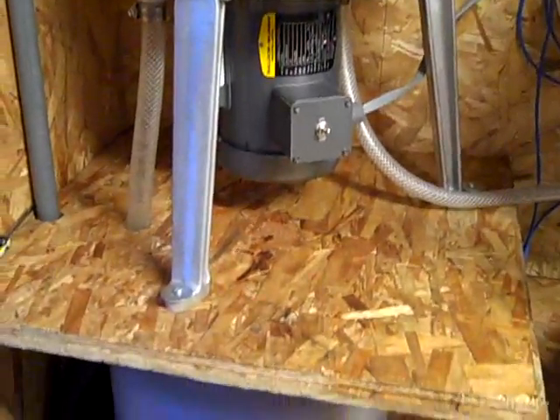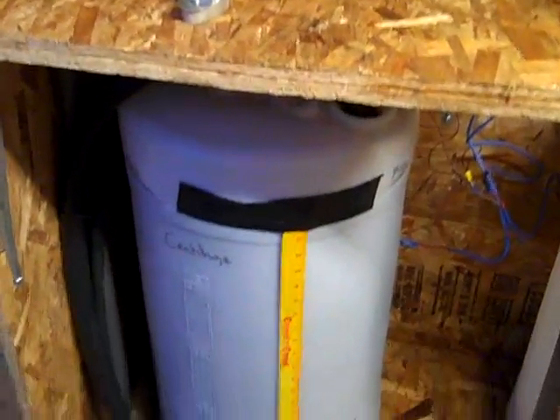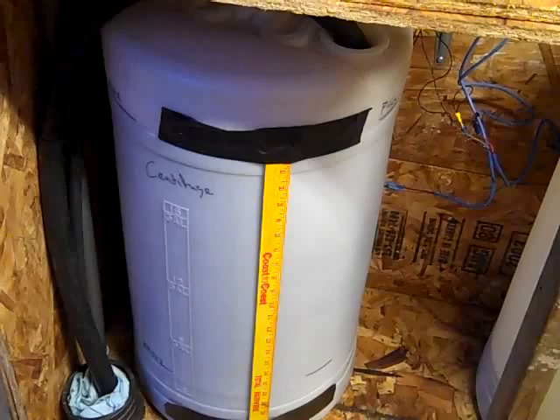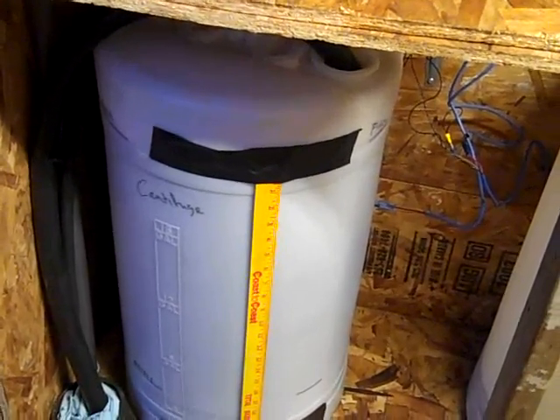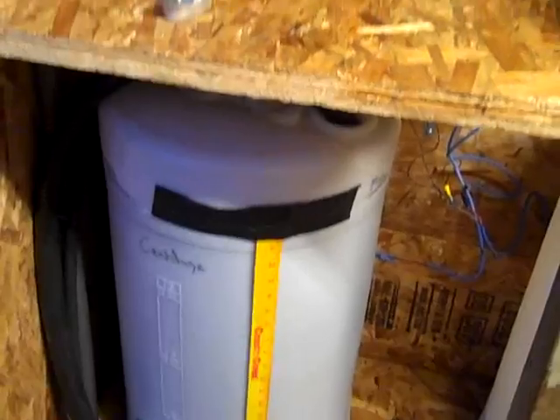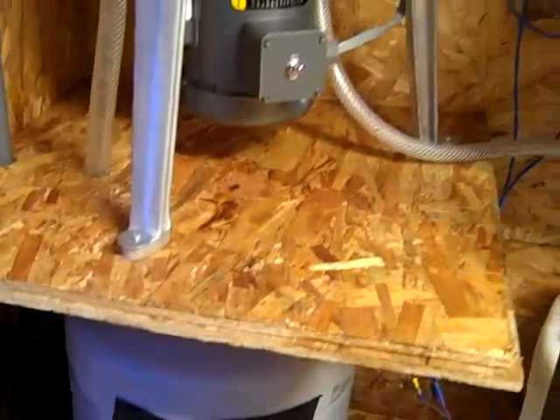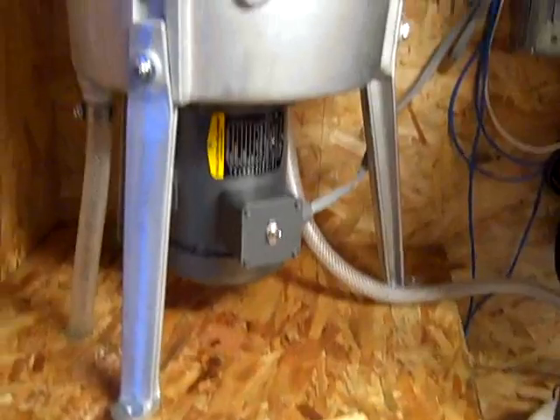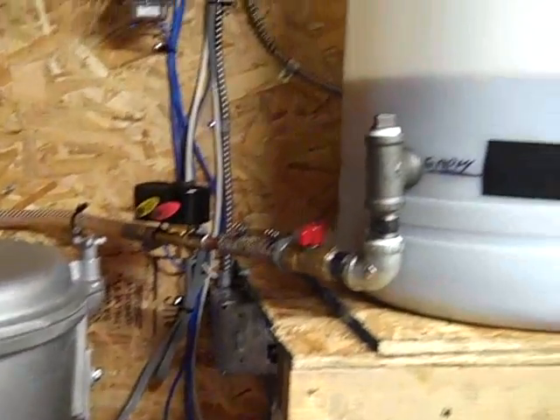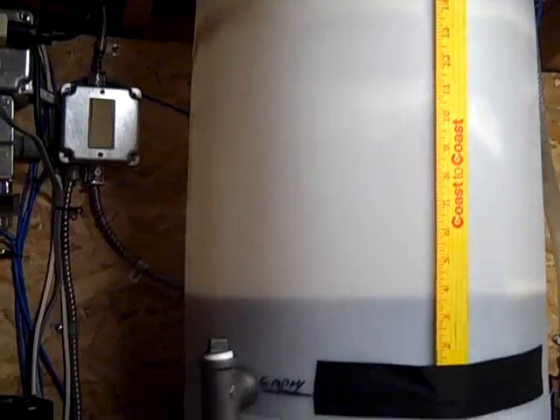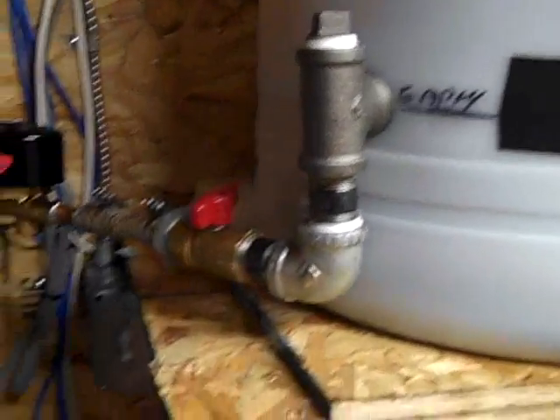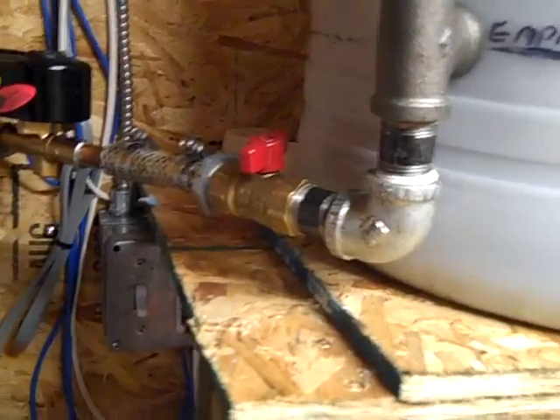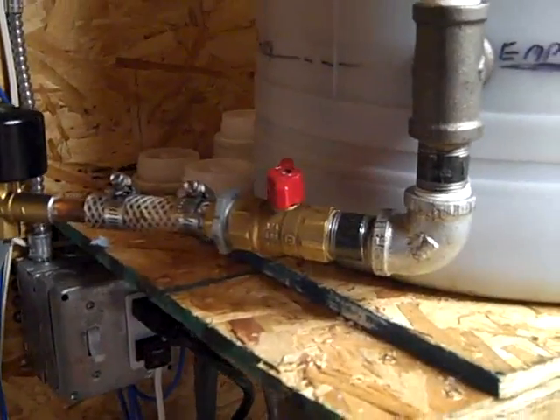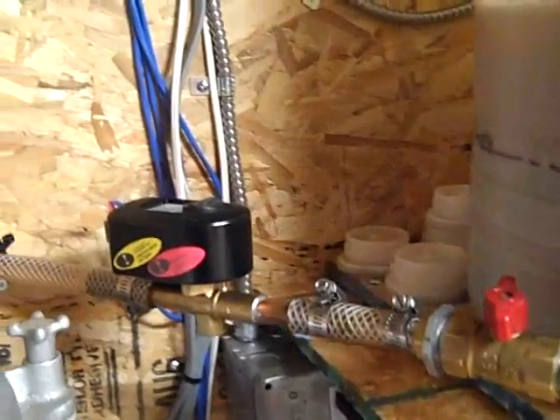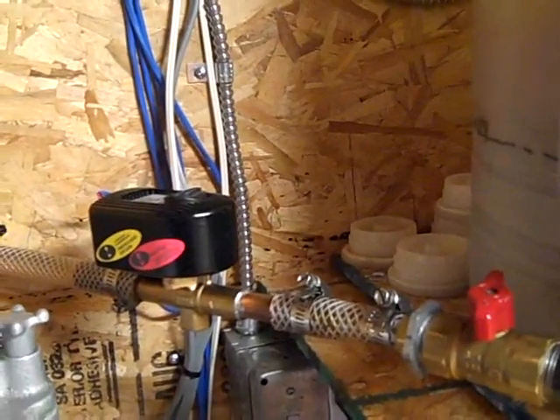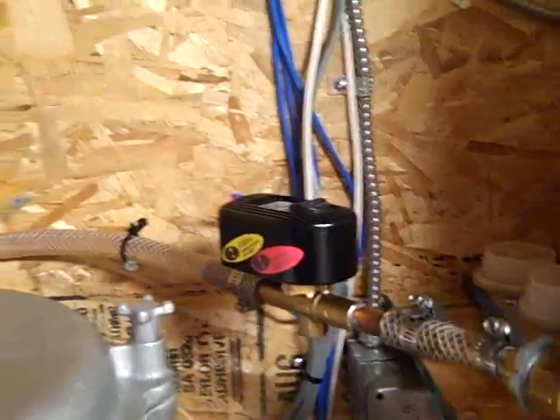What I also have, in the barrel that the centrifuge feeds into, is an additional float that also controls the centrifuge, so that if this barrel here is full, the centrifuge will not get turned on, and there's no way that it could be activated, regardless of how much oil is in the gravity barrel. So from the gravity barrel you can see we have a valve here which I adjust to adjust my flow, and then I have a motorized valve which allows the oil to flow or not, depending on whether the centrifuge is turned on or not.